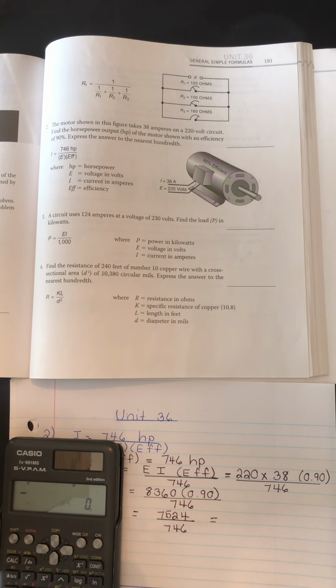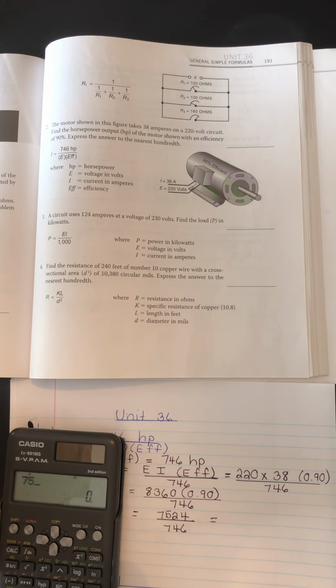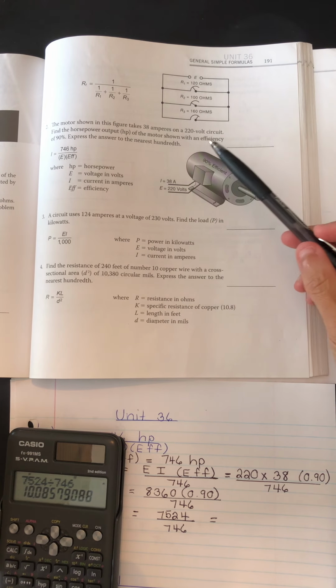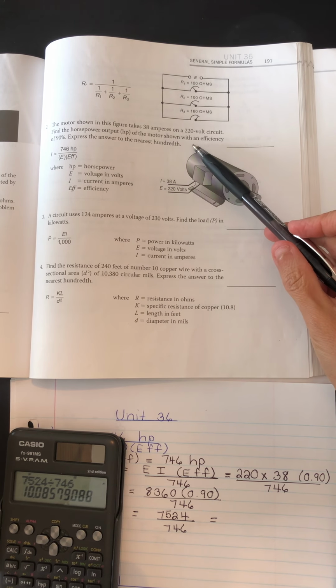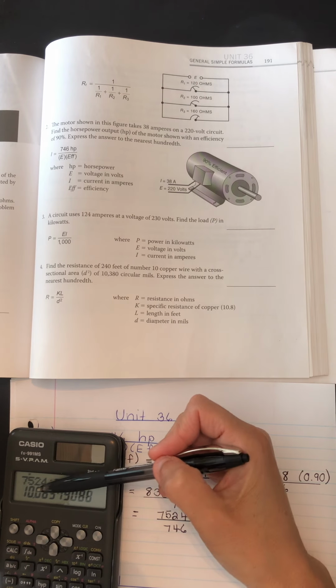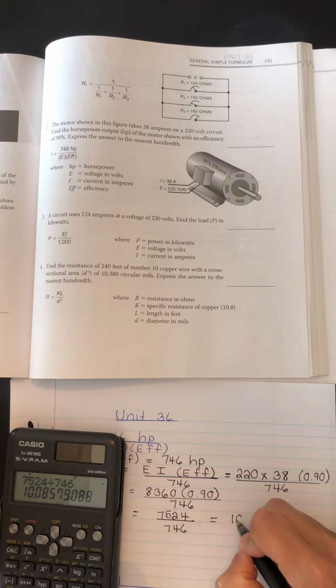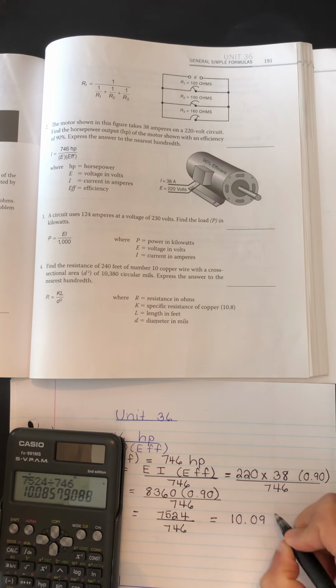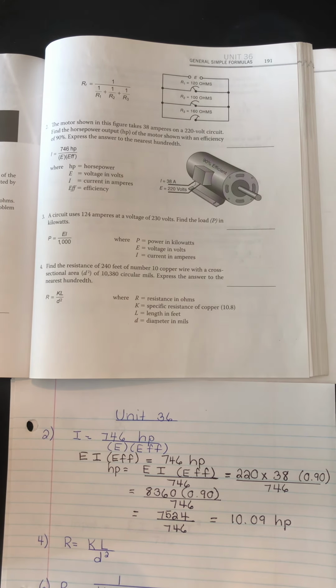Okay, so when we carry out that division, I'll show you this one with the calculator. So we have 7524 divided by 746, okay? And we're asked to round to the nearest 100th. So this would be 10.09. That would be the output power in horsepower.